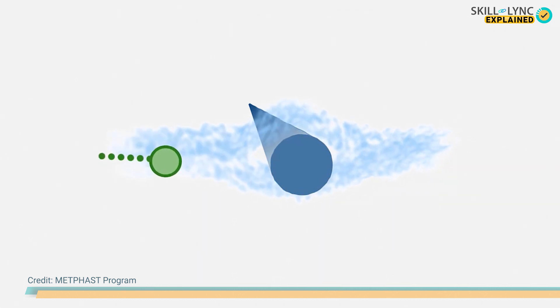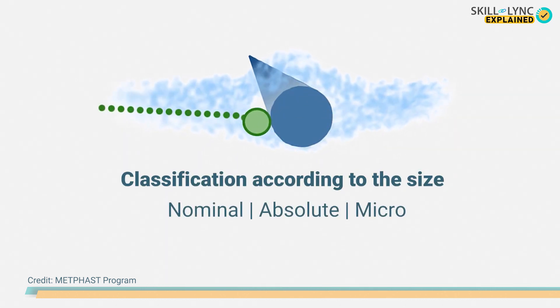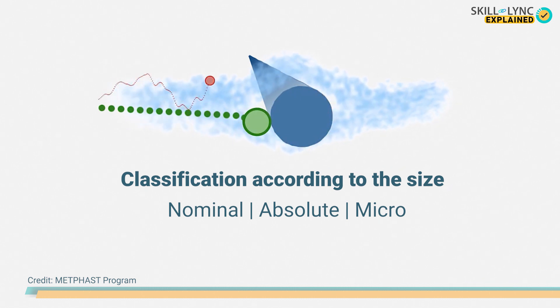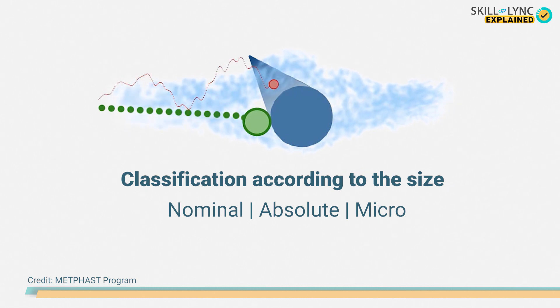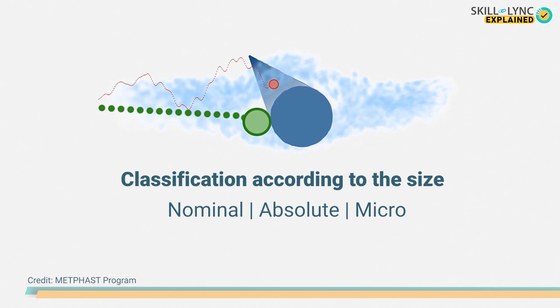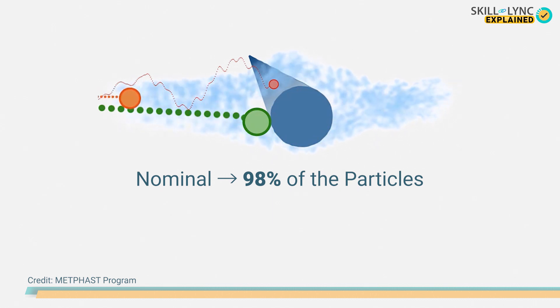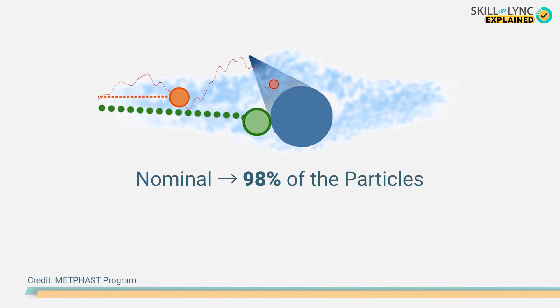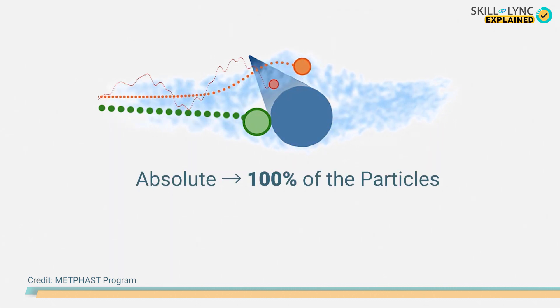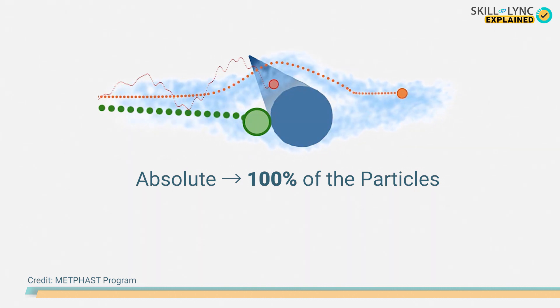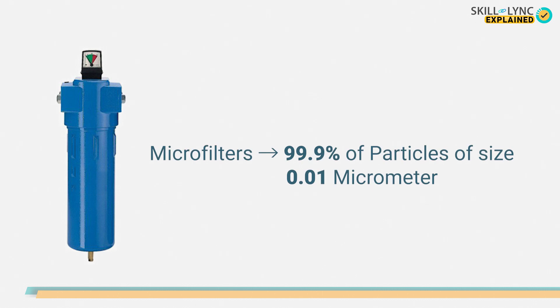Another classification of filters is done according to the size of particles they can filter. The size of the particles is measured in microns or micrometers. Filters with a nominal rating will block 98 percent of the particles, while a filter with an absolute rating will block 100 percent of the particles of the specified size.